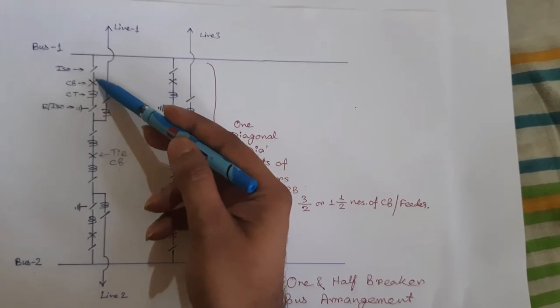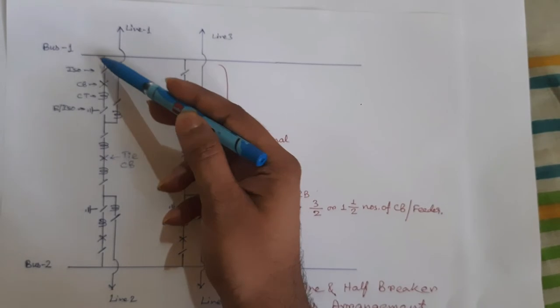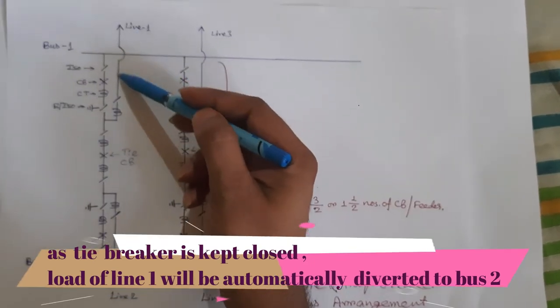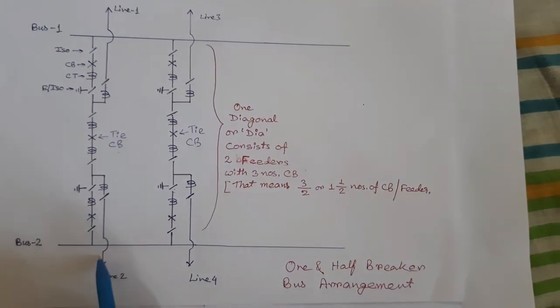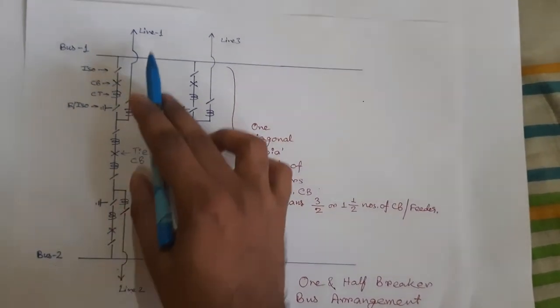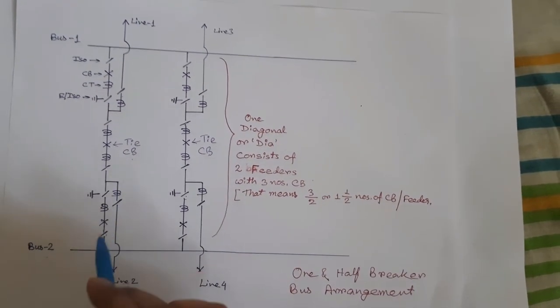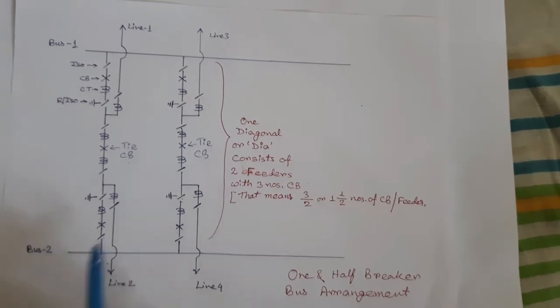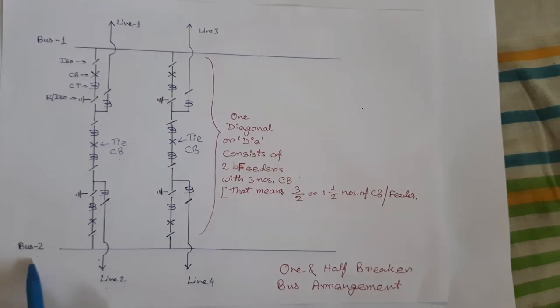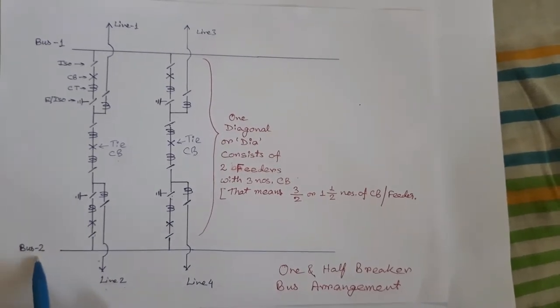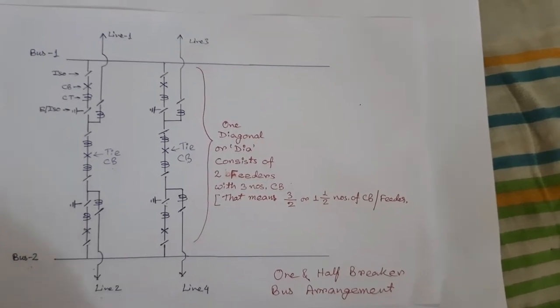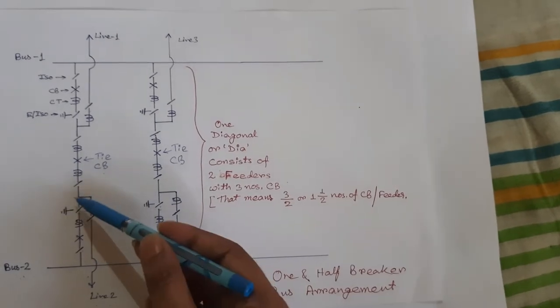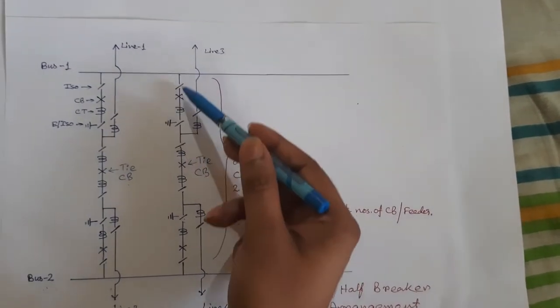Due to tripping of that circuit breaker, line 1 cannot take power through bus 1. But as the tie breaker is closed, the load of line 1 will automatically divert to bus 2. So load of both line 1 and line 2 will be fed through bus 2 during a fault in bus 1. Similarly, if a fault occurs in bus 2, all circuit breakers connected with bus 2 will trip to clear the fault. But there will be no power interruption in line 2 or line 4, because their load will automatically divert to bus 1 through the tie circuit breaker.